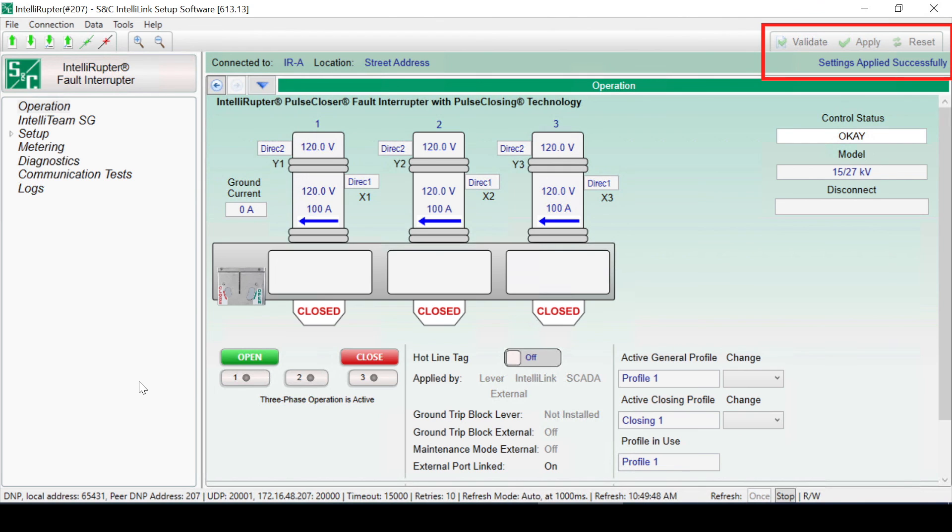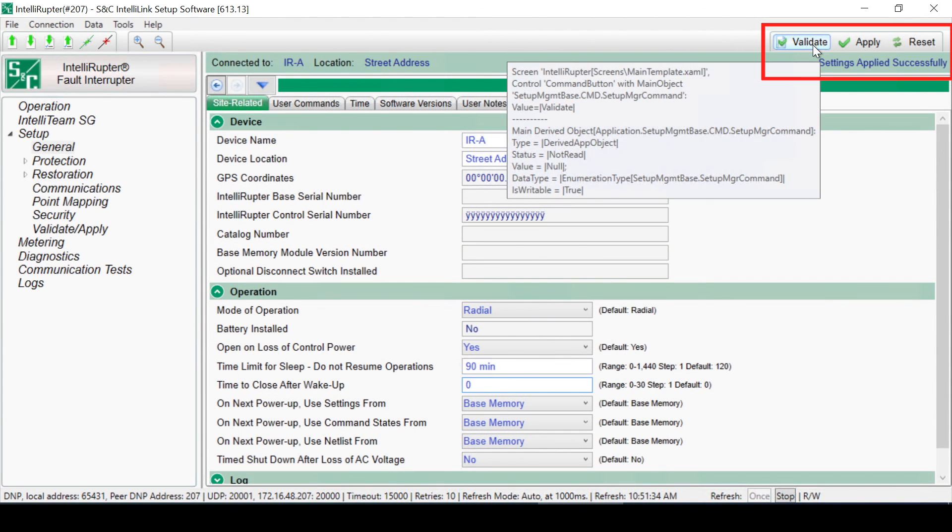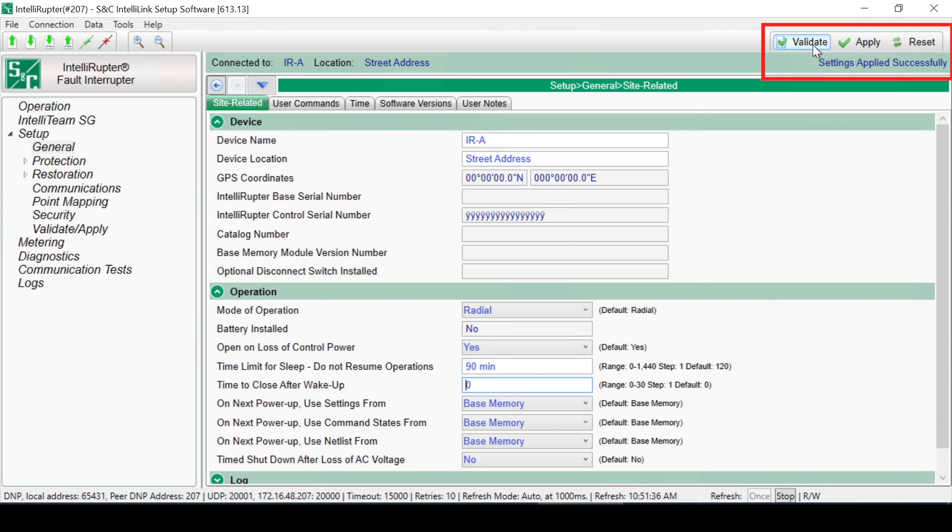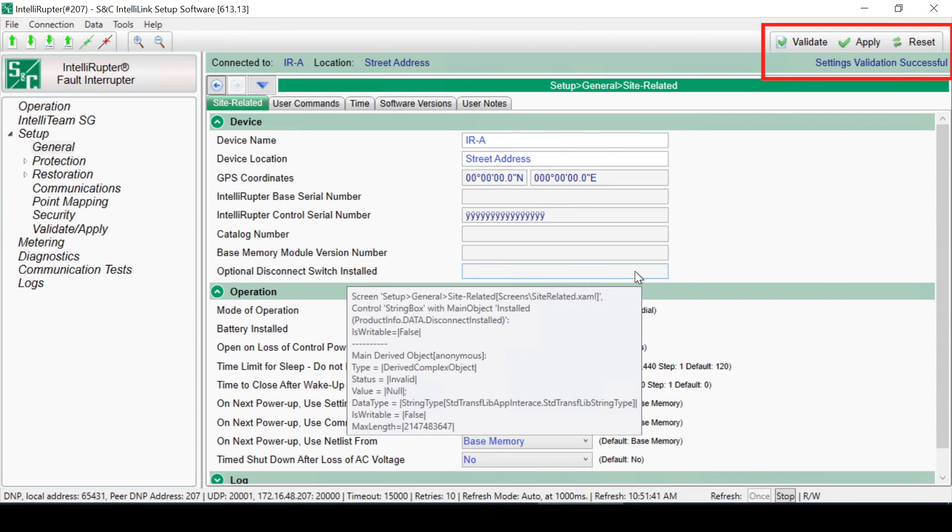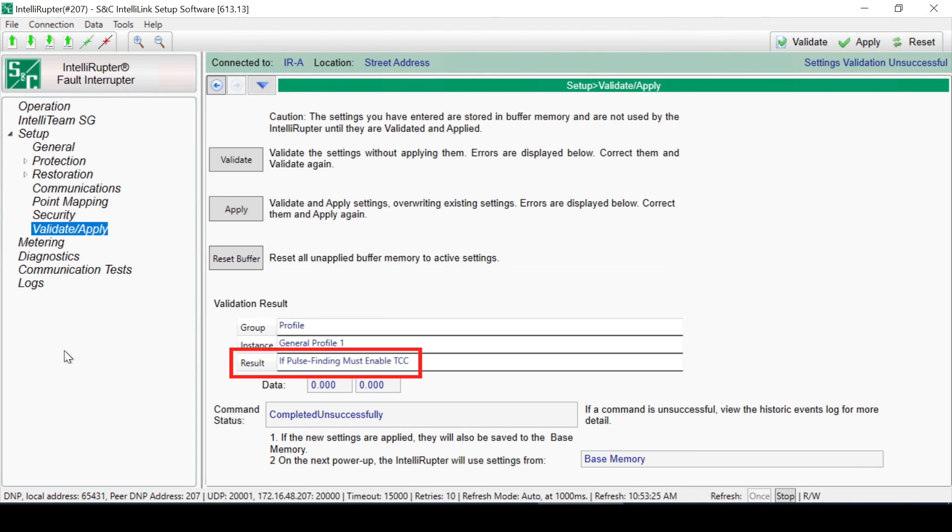Setting changes are only saved after passing a Validation check using the Validate and Apply buttons. After changing a setting, click on the Validate button to initiate a logical check of the pending changes for errors. If the validation procedure detects an error or inconsistency, it will be displayed in the Validation Result box found on the Setup Validate Apply screen so the errors can be fixed before applying changes to the control.